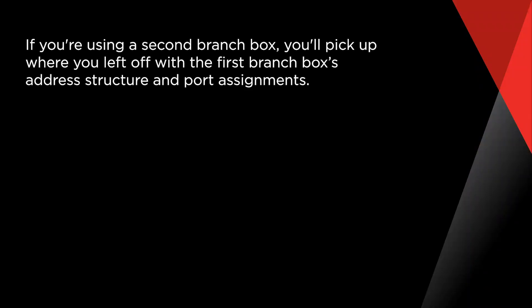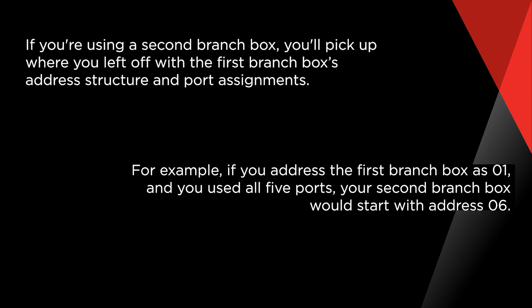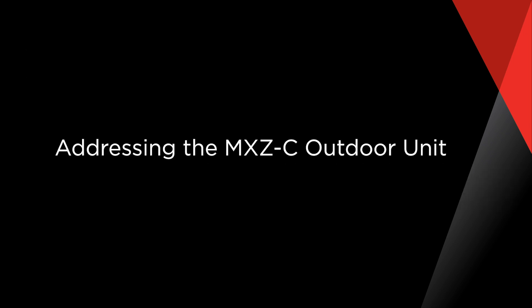If you're using a second branch box, you'll pick up where you left off with the first branch box's address structure and port assignments. For example, if you address the first branch box as 01 and you used all five ports, your second branch box would start with address 06. Once you have addressed the branch box, move on to the outdoor unit.